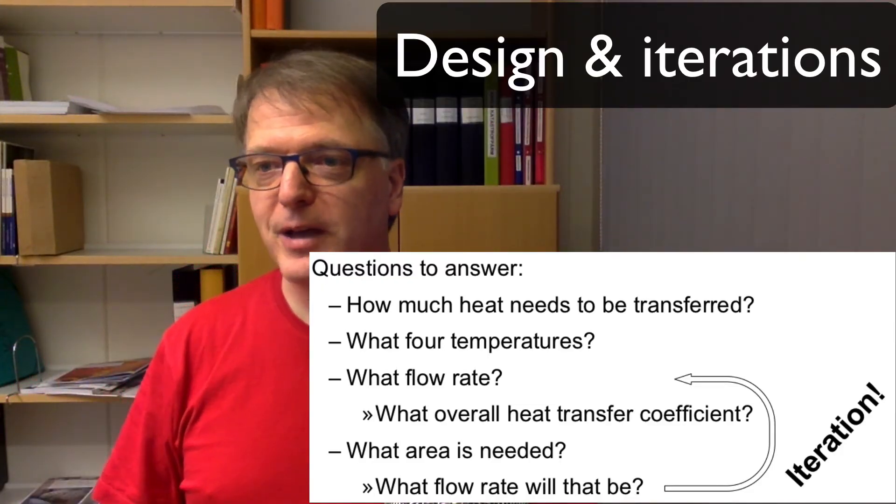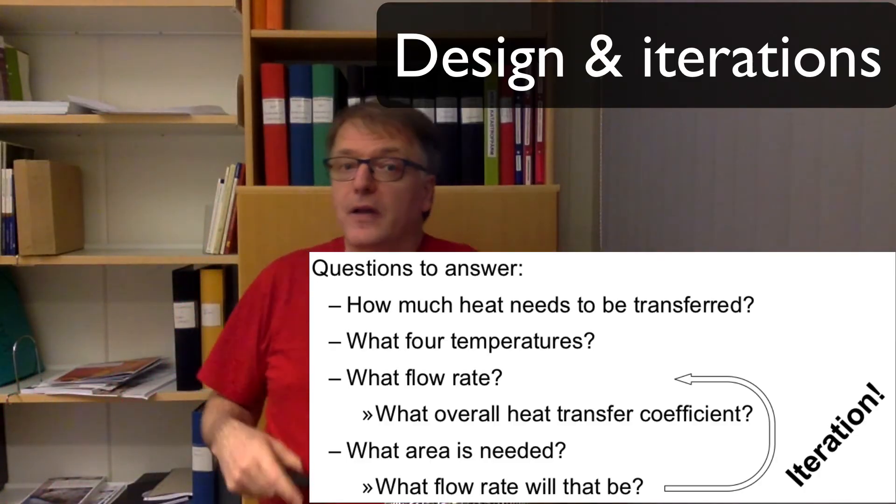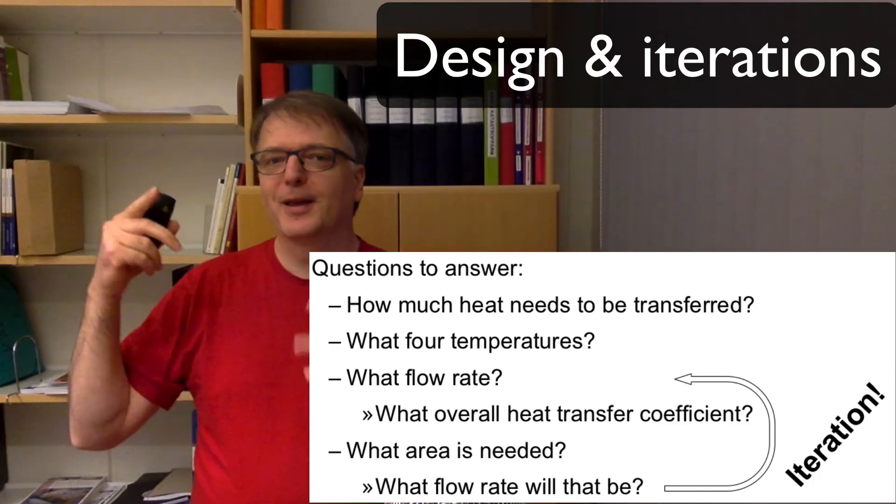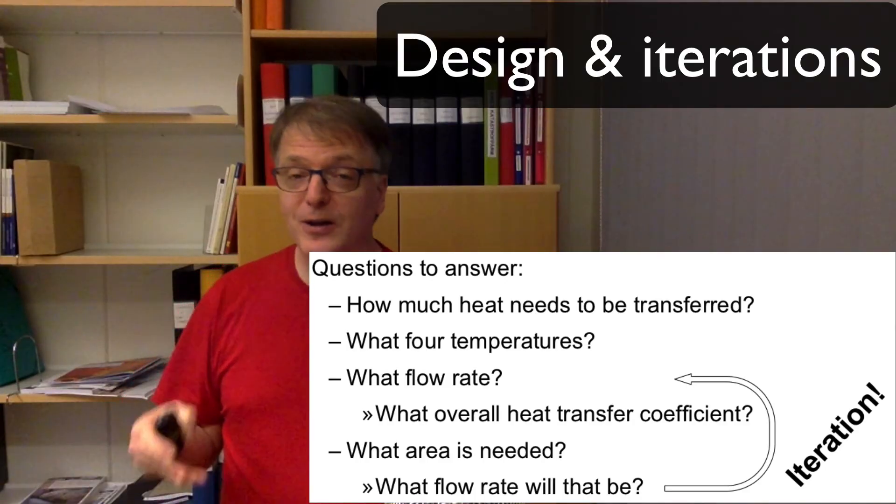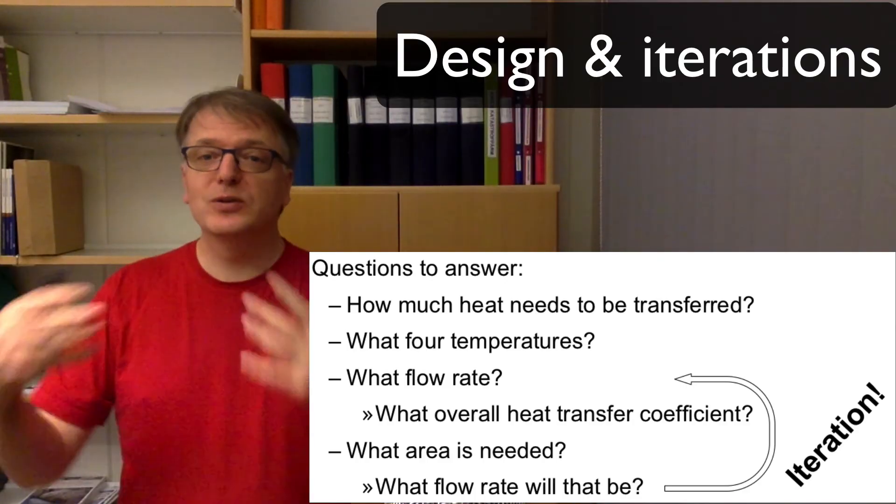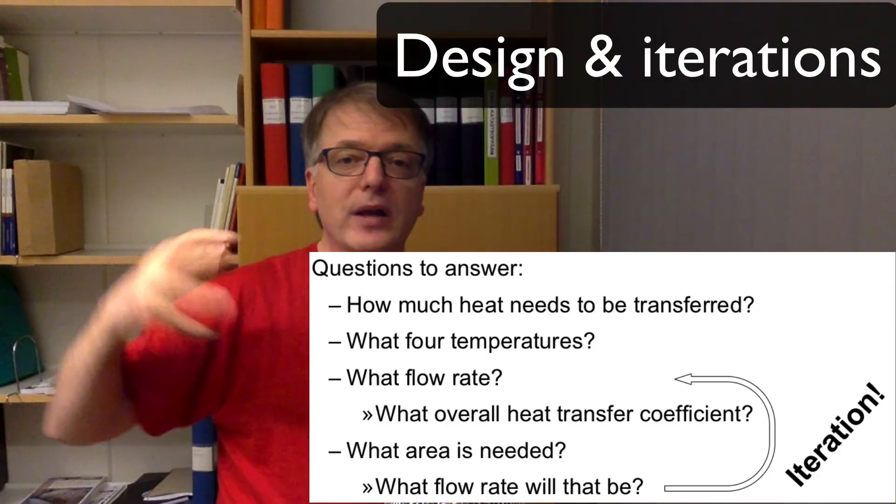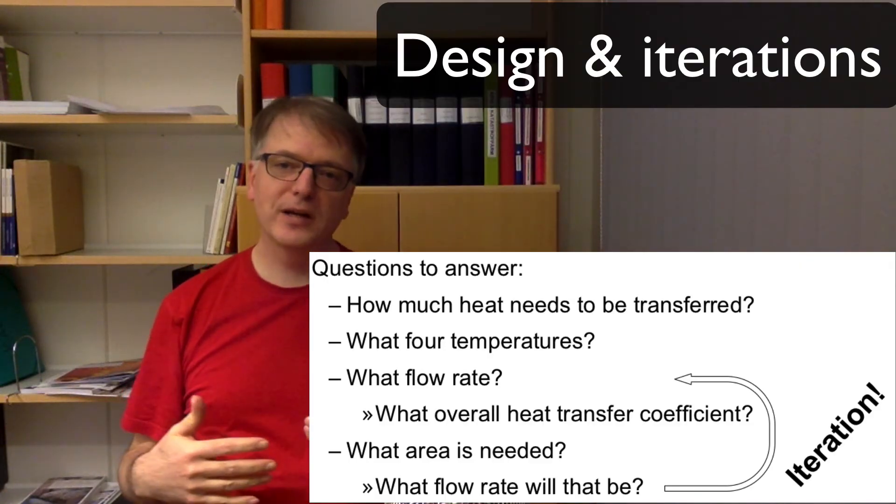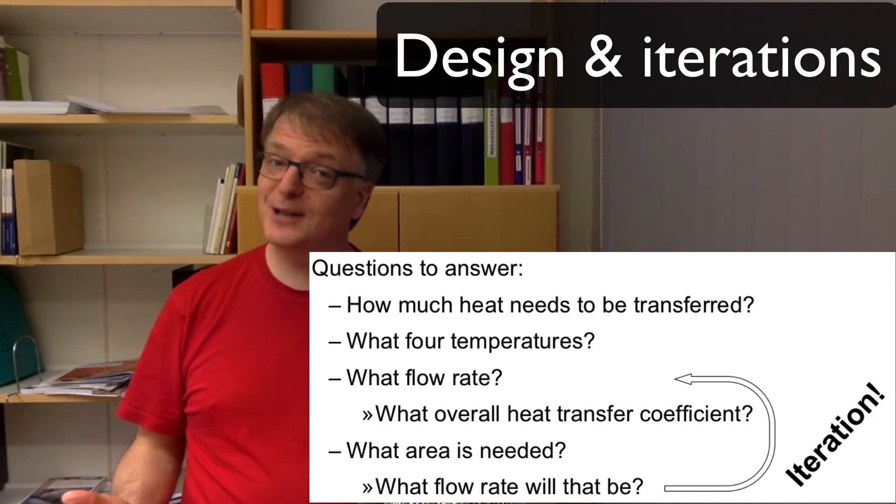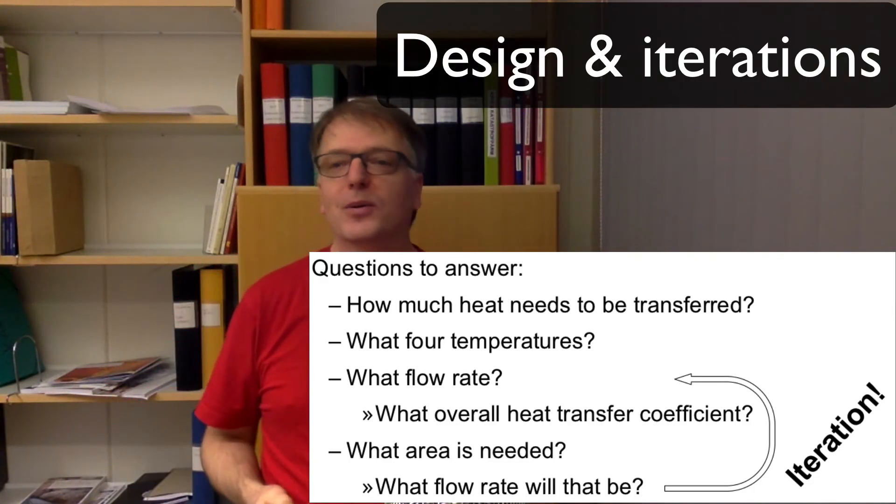Which in turn will influence the flow rate. Now the problem is you have to do an iteration here. You have to guess a flow rate or just set a flow rate you would like to have, and then you do the calculations and then you do this design, whatever you do—a plate heat exchanger or whatever. When you've done all the design choices you can calculate the flow rate, and if that flow rate is different than the one you used before, then you need to redo your calculations and continue until it all fits.